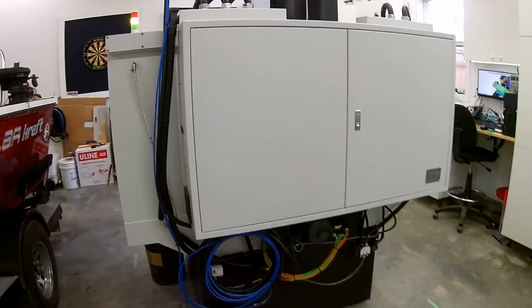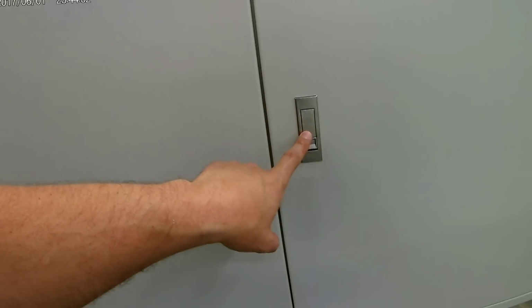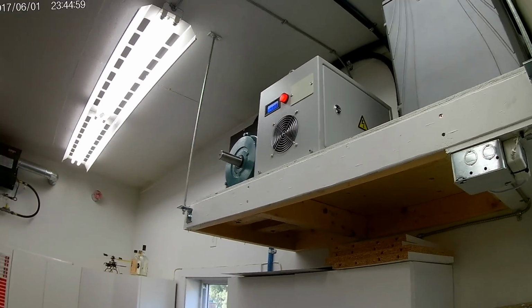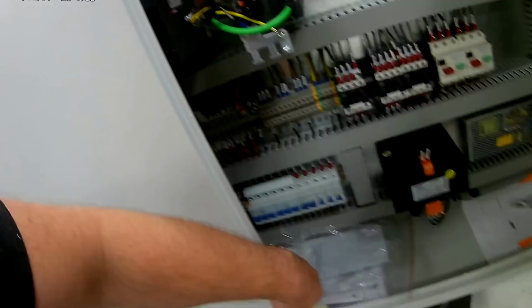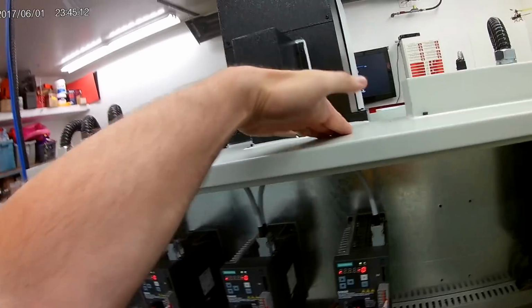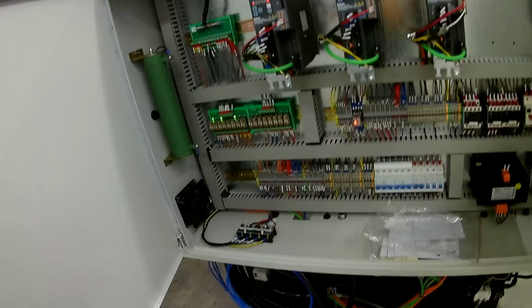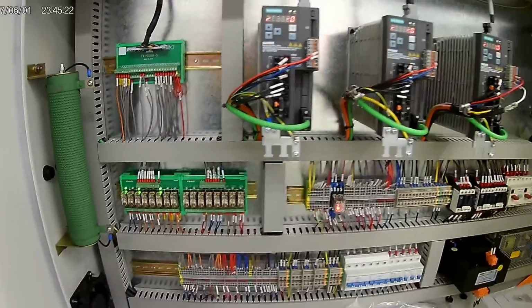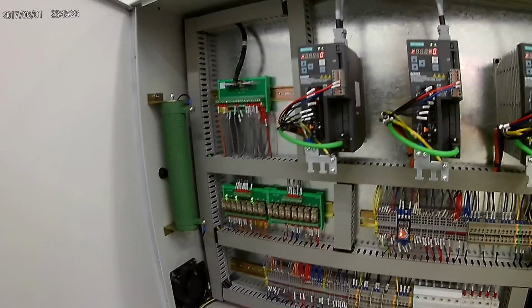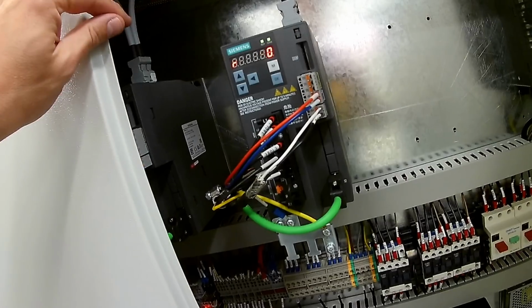Around the back here is the electronics cabinet. So we'll open it up. The one thing I would have suggested is to have this have a lock and key like the transformer does up there. Probably really hard for you to see, but just so people don't inadvertently open it. In our case, there's 430 volts here, which according to my electrician is electrician-killing power. So that's the one thing. A guy could just keep the key up top, but at least it'll keep people from opening it that shouldn't. So here are the advanced drivers. Wiring's very nice and tidy. We checked every single screw in here. There wasn't anything loose. So the assembly quality seems to be quite good.